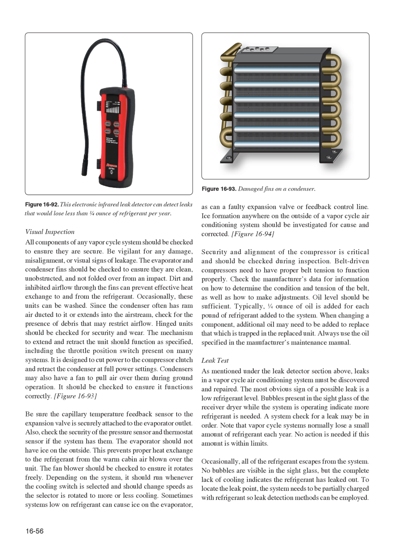Belt-driven compressors need to have proper belt tension to function properly. Check the manufacturer's data for information on how to determine the condition and tension of the belt, as well as how to make adjustments. Oil level should be sufficient. Typically, 1/4 ounce of oil is added for each pound of refrigerant added to the system. When changing a component, additional oil may need to be added to replace that which is trapped in the replaced unit.